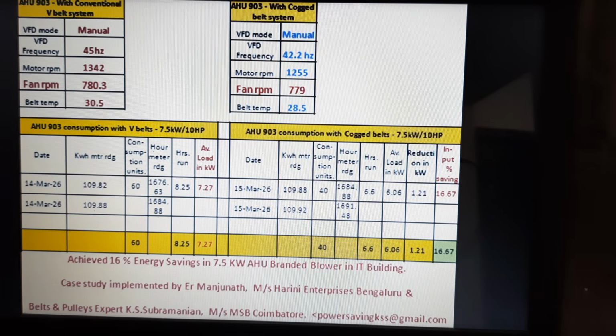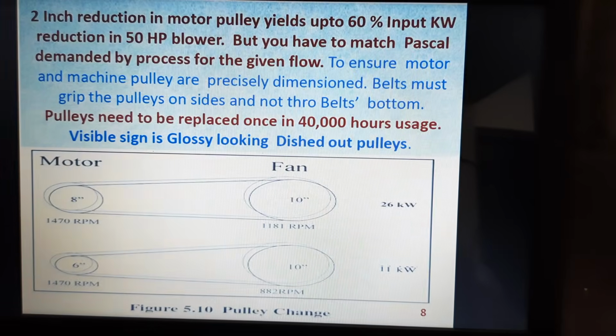And you can see that after changing to redesigned pulleys and belts, the VFD frequency was kept at 42 Hertz only, and the same blower RPM was maintained. The output is the same, blower RPM around 780, but you can see the input kilowatt has dropped from 7.27 to 6.06, almost 16% savings, in this branded AHU blower in the IT building. This was also done by the MSB team.